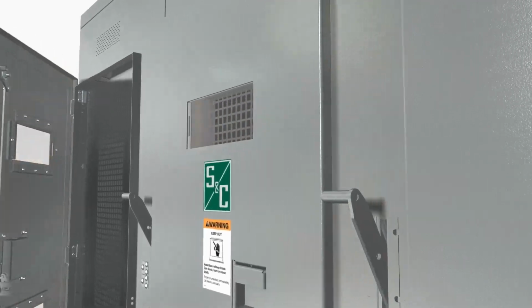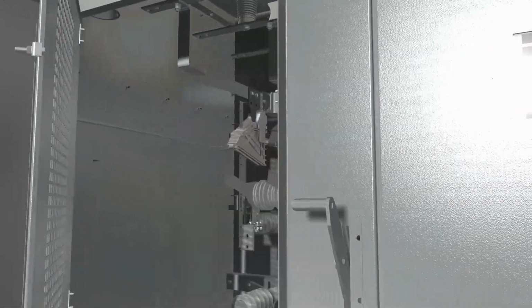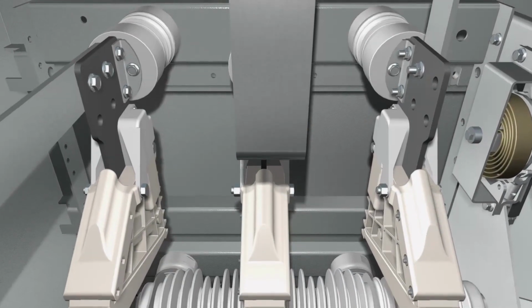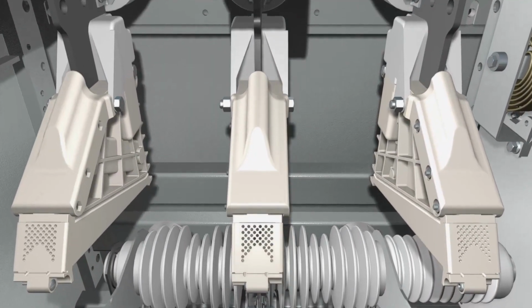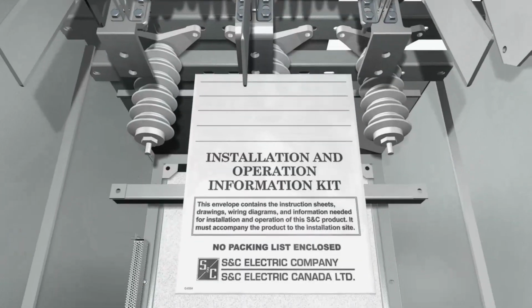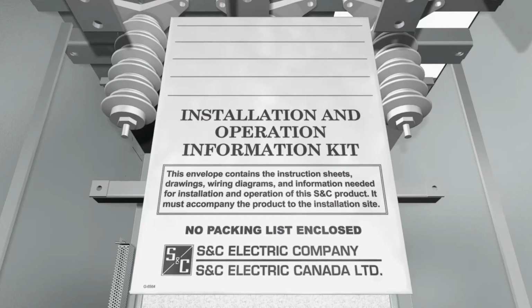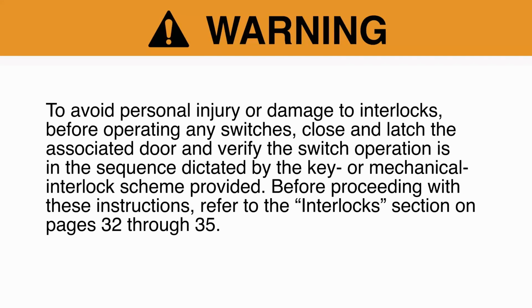Step 14. Check operation of manually operated switches. Separate instruction sheets on manually operated load break switches are included in the Installation and Operation Information Kit provided with the switchgear. Warning: to avoid personal injury or damage to interlocks, before operating any switches, close and latch the associated door and verify the switch operation is in the sequence dictated by the key or mechanical interlock scheme provided. Before proceeding with these instructions, refer to the interlock section on pages 32 through 35 of the written instructions.